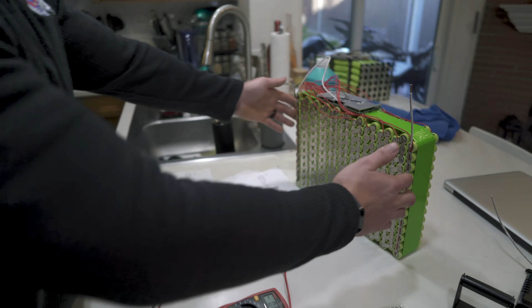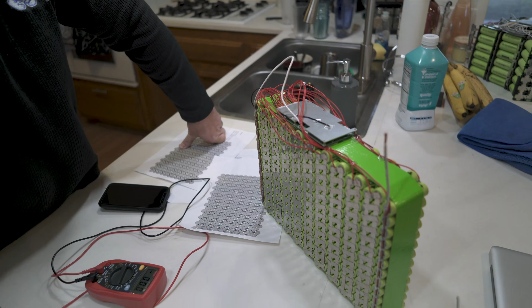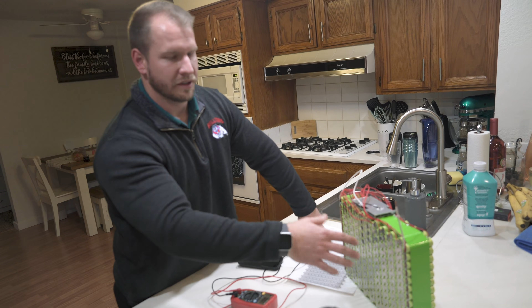And so the thought now is use the BMS just for charging, and then the discharging can happen without being balanced. And then when you charge it, as long as you're not going below 60 volts, generally you're not going to be risking any of the batteries. And then when you're charging, it'll just rebalance all the cells out, so it'll discharge, maybe be slightly imbalanced at the end of the discharge, but the charge will balance them all back out.